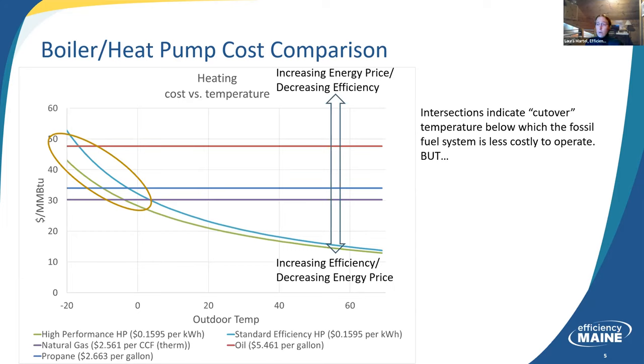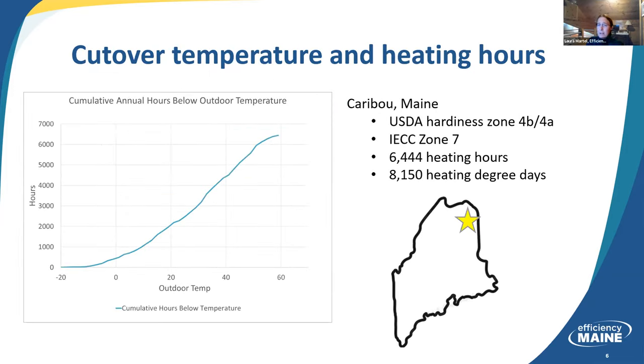So there's a couple of things to point out here. One is that those crossover points happen close to or down below 0 degrees. So we're talking cold. This isn't just chilly. This is cold temperatures. And so it looks like there are going to be times of the year where you'd be better off running your oil boiler than your heat pump. Well, not your oil boiler, because that one goes off the chart entirely. You'd have to be down at minus 25 or minus 30. But let's say for propane, there are going to be times of year when it's less expensive to operate your propane boiler than your heat pump. But there's some more to take into consideration. So I'm going to take you through a couple of charts here. There's going to be a bit of a buildup. Bear with me. I think the ultimate conclusion will be worth the trip.